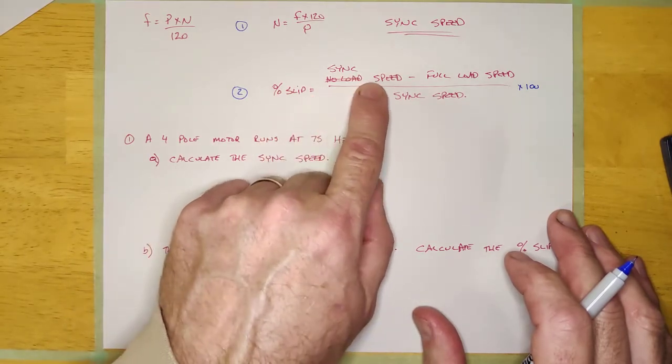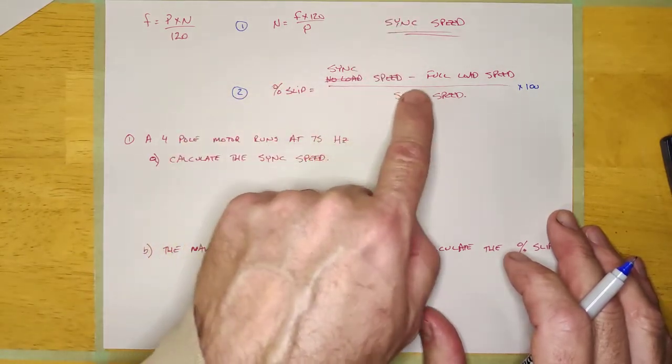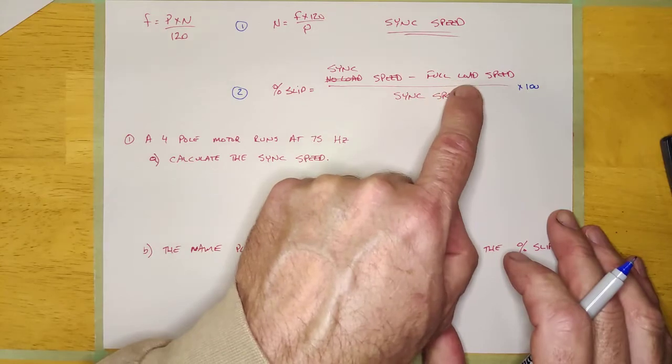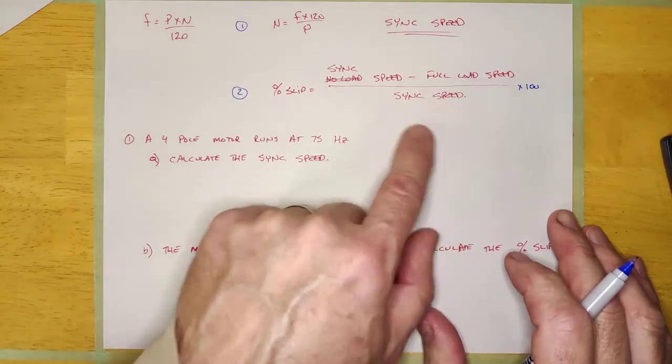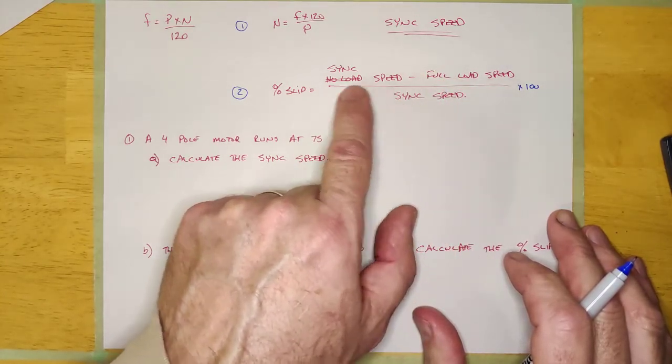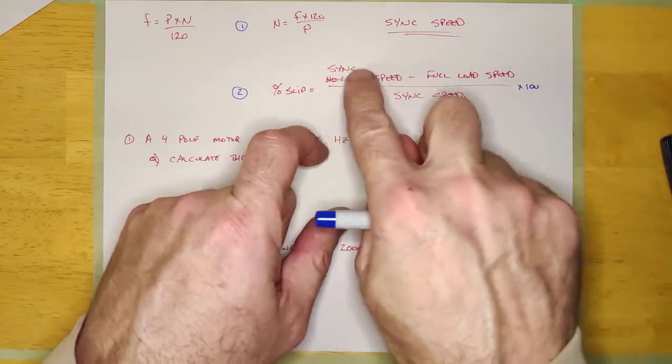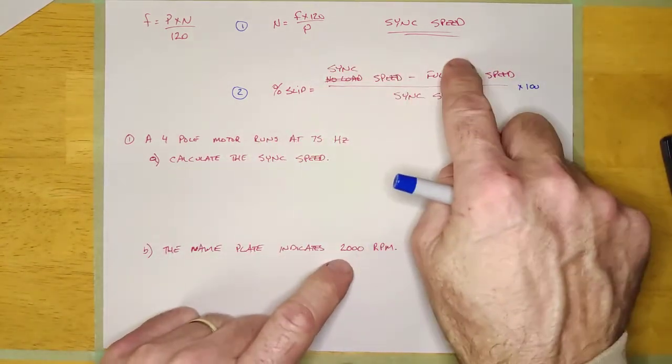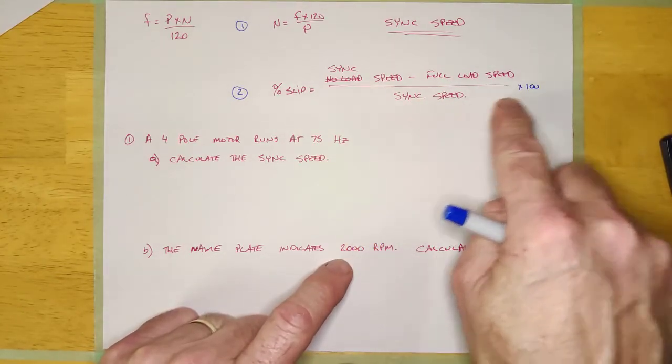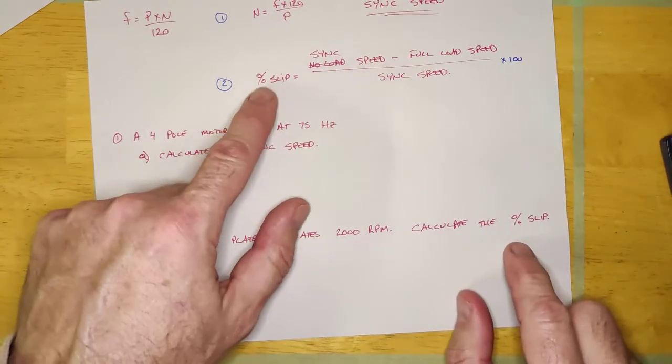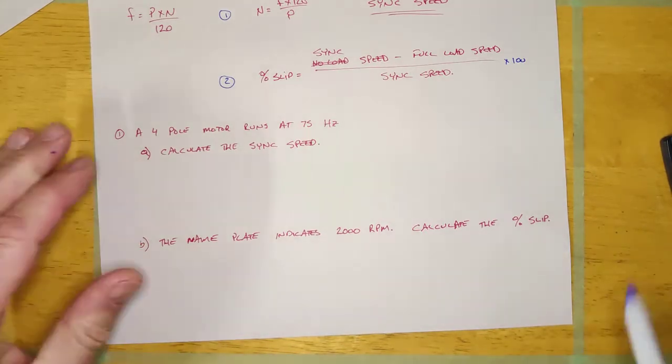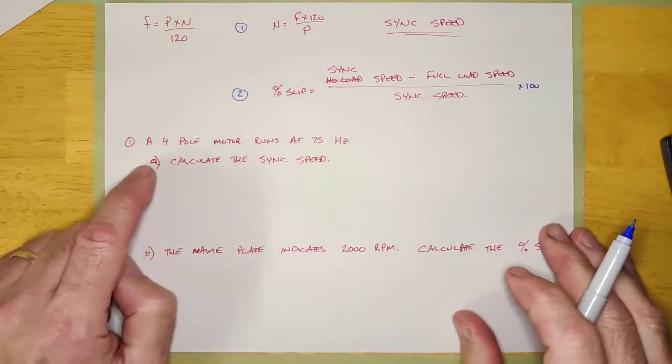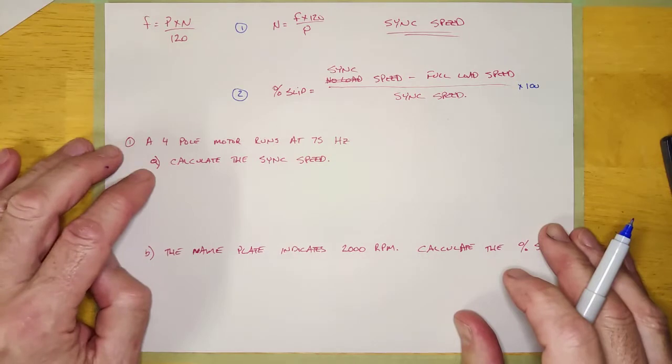And it is the sync speed, which we can calculate, minus the actual speed, full load speed, or the nameplate speed. All over the sync speed. And so basically what this top is is the sync speed minus the full load speed. So it's the amount it's slipping divided by the sync speed. And then times 100 to get it into a percentage. And so as an example, we're just going to take up this question here.